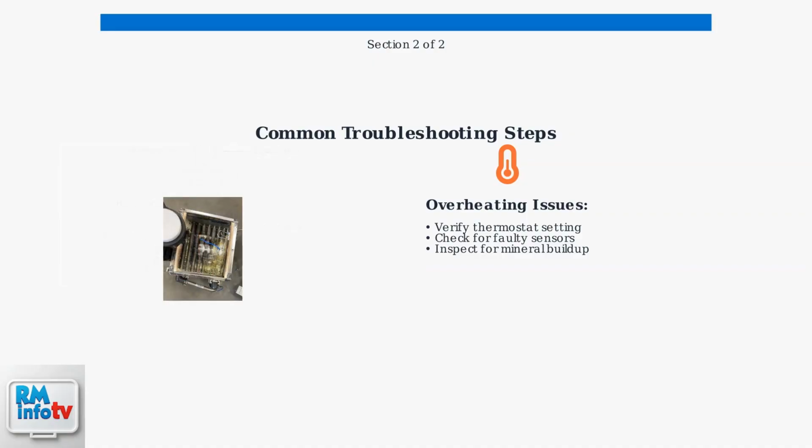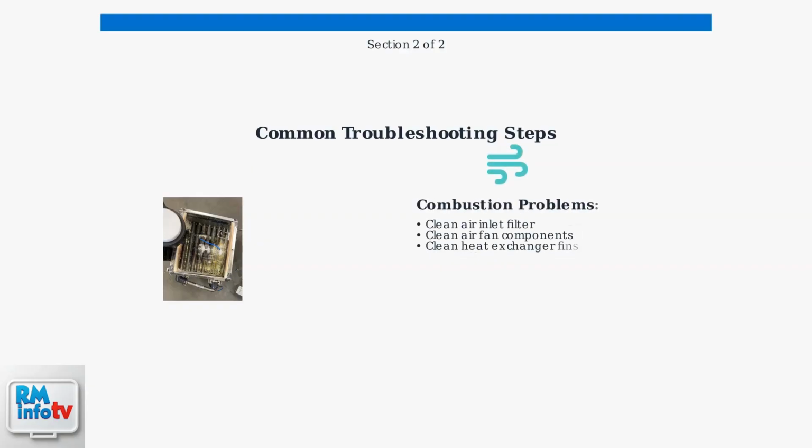Here's what a dirty heat exchanger looks like. This mineral buildup can cause overheating and reduced efficiency. Combustion problems often stem from dirty components that need regular cleaning to maintain proper airflow and operation.